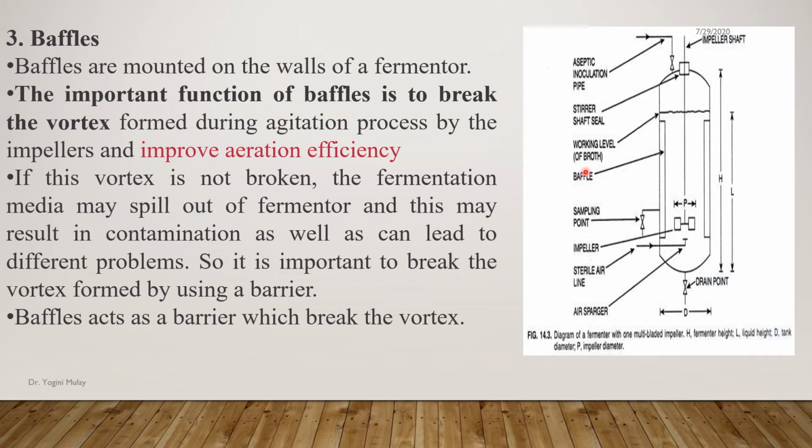Baffles are mounted on the walls of the fermenter. See, this is the fermenter, and you can see this. This is nothing but the baffle. The function of the baffle is to break the vortex which is formed during the agitation process, and thus it helps to improve the aeration efficiency. Now, what will happen if the vortex which is created by the agitation is not broken?